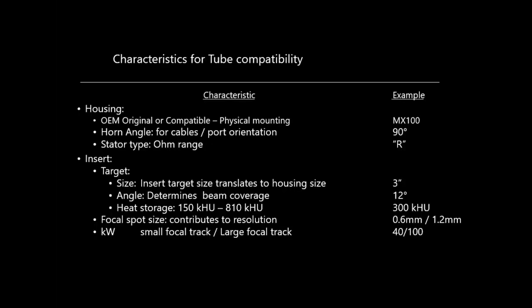So the characteristics you need in the tube, particularly if you're looking at a compatible tube as opposed to buying from the OEM, the original compatible housing. That has to do with the mounting, the typical examples of MX100, one of the most common tubes in our market. You have a horn angle, which is the angle between the port and the receptacles, so that when you install it, it's pointed correctly in the cable.